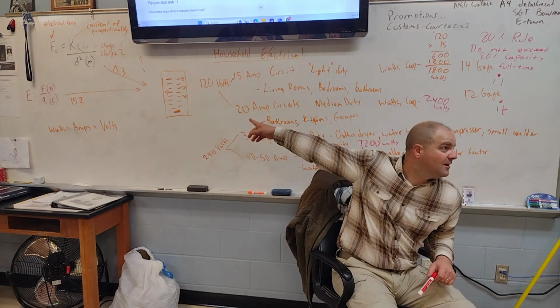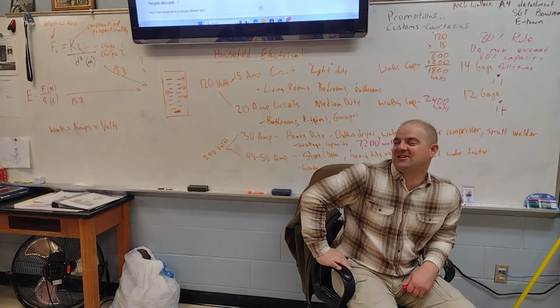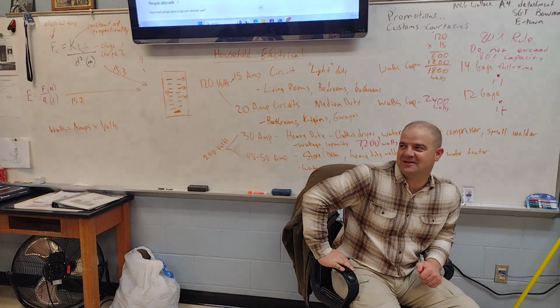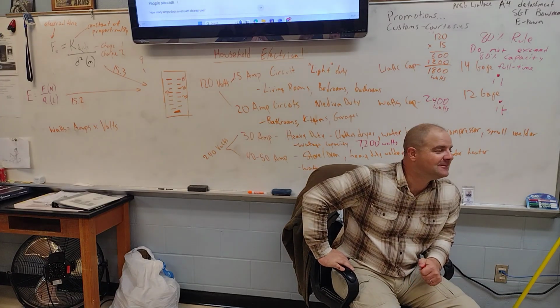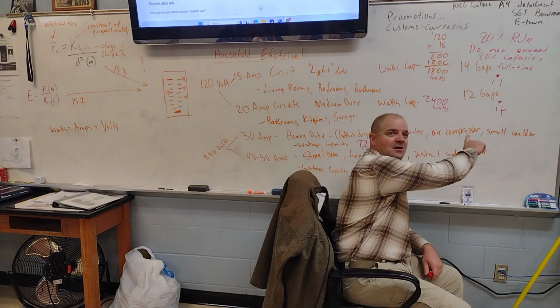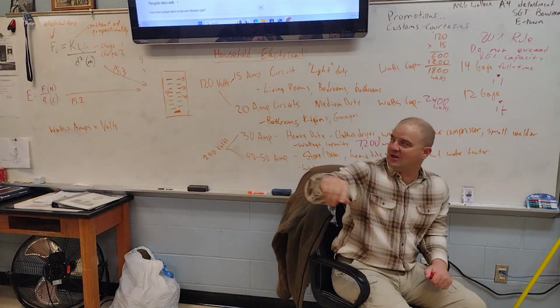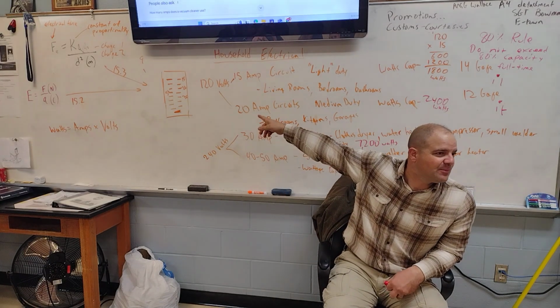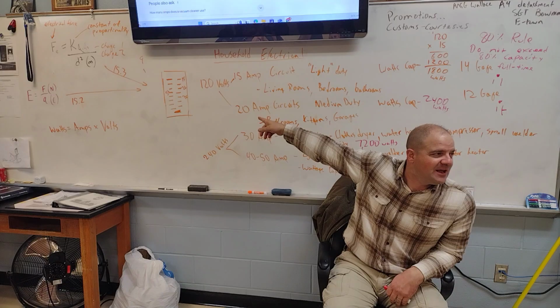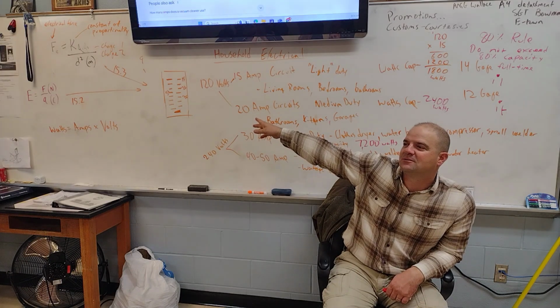Now what's it going to do if it tries to supply that much power? Overheat. It's going to trip the breaker. But what else have I seen? I've owned several homes. I've seen people, they want to have that so they can run their higher power circular saw or whatever it is. They'll switch out the circuit breaker for a 20 amp breaker, but what haven't they switched?